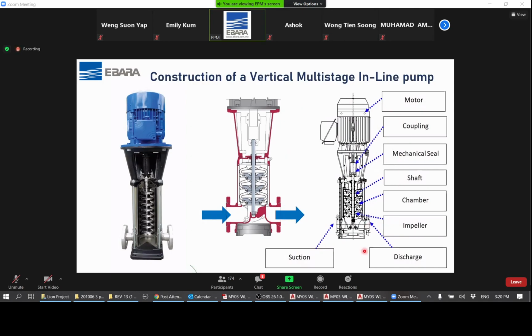So you can see from the construction here of how the pump is like. The motor will be on top and the coupling between the motor to the pump. And on top of the pump, usually you will have a mechanical seal. There are many types of seals for this type of pump, but the most common will be a cartridge seal. Then you have the shaft and you have the chamber and the impellers, and all these are rotating at 2900 RPM, the shaft and the impeller, okay? So with that, it is able to build the pressure of the water when it goes in and out.